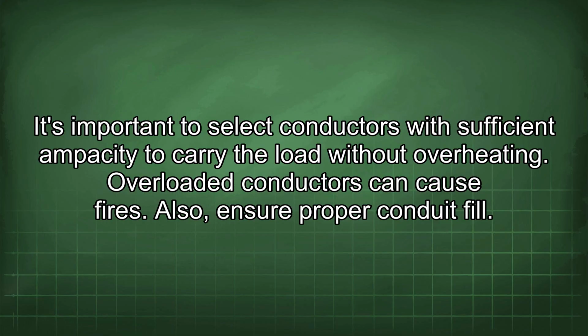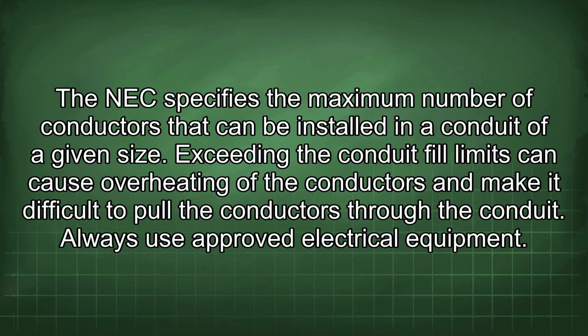Also, ensure proper conduit fill. The NEC specifies the maximum number of conductors that can be installed in a conduit of a given size. Exceeding the conduit fill limits can cause overheating of the conductors and make it difficult to pull the conductors through the conduit. Always use approved electrical equipment.